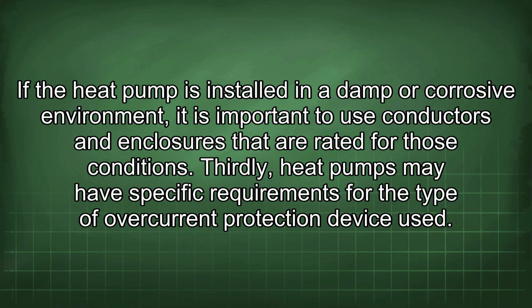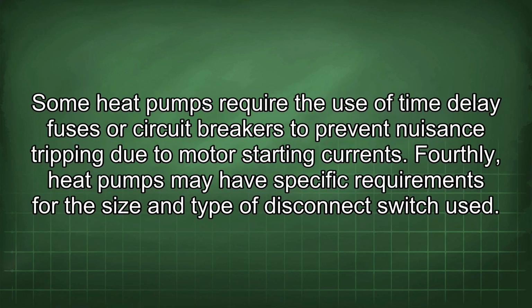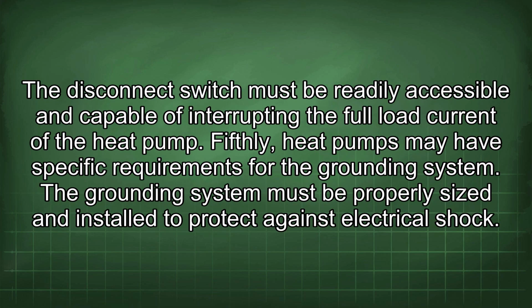Thirdly, heat pumps may have specific requirements for the type of overcurrent protection device used. Some heat pumps require the use of time delay fuses or circuit breakers to prevent nuisance tripping due to motor starting currents. Fourthly, heat pumps may have specific requirements for the size and type of disconnect switch used. The disconnect switch must be readily accessible and capable of interrupting the full load current of the heat pump. Fifthly, heat pumps may have specific requirements for the grounding system. The grounding system must be properly sized and installed to protect against electrical shock.